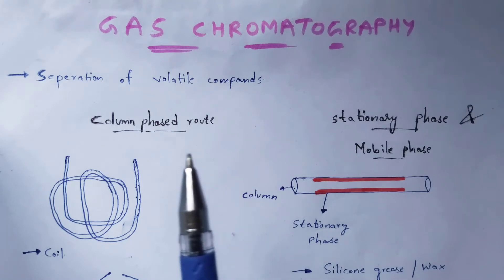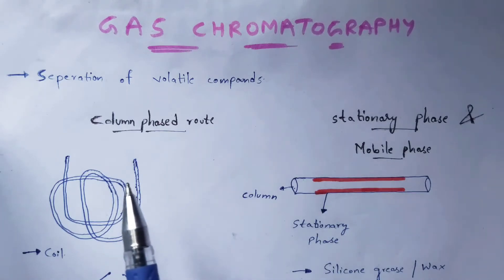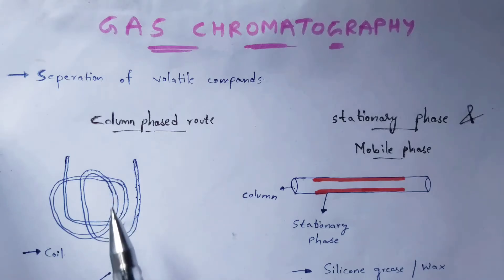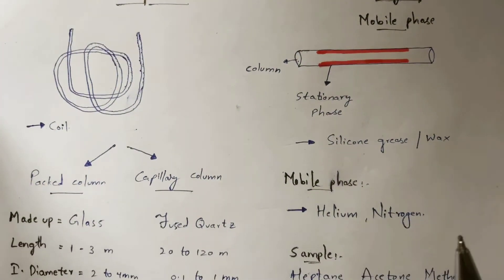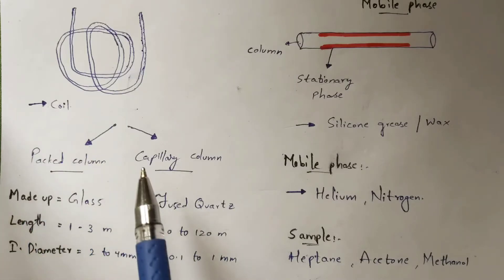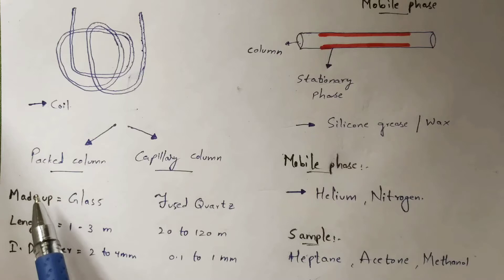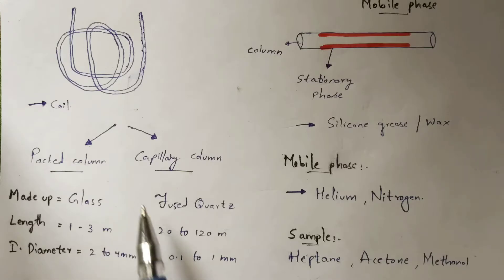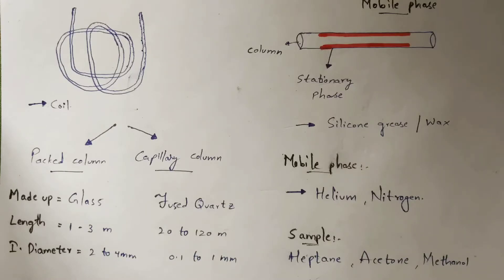Let us discuss the apparatus and process for gas chromatography. The column used should be a coil-like structure. There are two types of columns: packed column and capillary column. The packed column is made of glass with a length of 1 to 3 meters and an internal diameter of 2 to 4 millimeters. The capillary column is made of fused quartz with a length of 20 to 120 meters and an internal diameter of 0.1 to 1 millimeter.